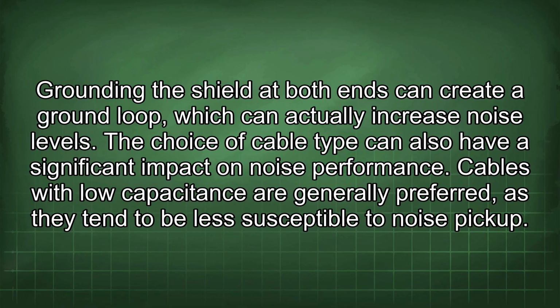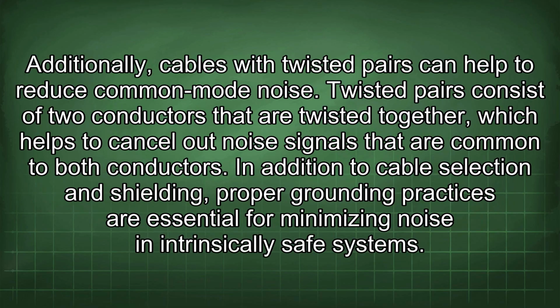The choice of cable type can also have a significant impact on noise performance. Cables with low capacitance are generally preferred, as they tend to be less susceptible to noise pickup. Additionally, cables with twisted pairs can help to reduce common mode noise. Twisted pairs consist of two conductors that are twisted together, which helps to cancel out noise signals that are common to both conductors.